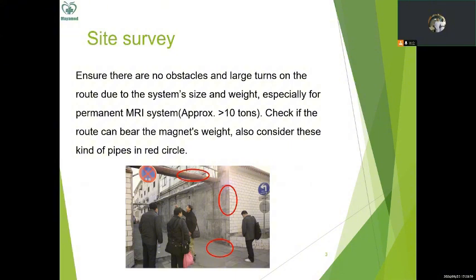So if we want to make sure everything is okay for the permanent MRI before the magnet entry, we must ensure that there are no obstacles and large turns on the route, due to the system size and weight. We should check all the routing from the train to the hospital entry to the department entry, and we need to check if the route can bear the magnet's weight. We mentioned that it's more than 10 tons. And also we must consider this kind of pipes in the red circle in the image. Things like this may block the entries. That is very important for permanent MRI systems.